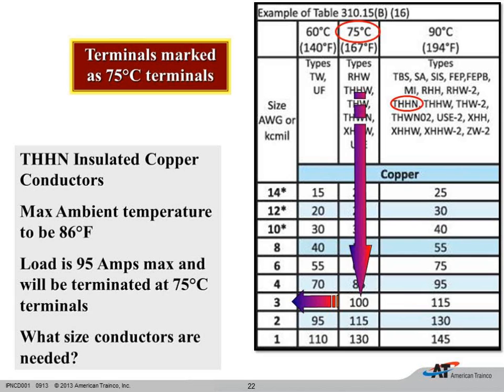So here is the table that we've had since the first code book I ever saw, which was in 1971, and back then it was titled 310.16. In 2011, they did change that to 310.15(B)(16), and this slide is very interactive, and you can see that we have some conditions on the side here. If the terminals are marked at 75 degrees Celsius, this is a nice little process that combines 110.14(C) along with 310.15(B)(16) and gives you a chance to be very confident in the size of the conductor that you need.